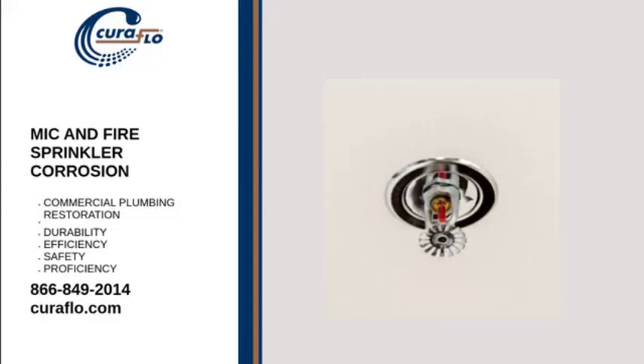Solutions: when MIC is detected in a fire protection system, the system should be evaluated to establish the severity and extent of MIC. There is unfortunately no universal solution to fire sprinkler repair. In some cases, it may be possible to clean the portions affected to remove obstructions, while in other scenarios, parts of the system may have to be replaced. This can be done by fire sprinkler repair companies specializing in commercial pipe replacement.